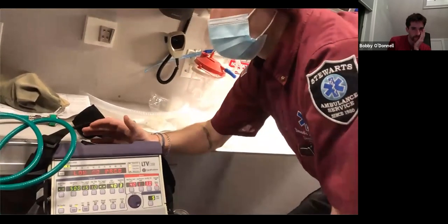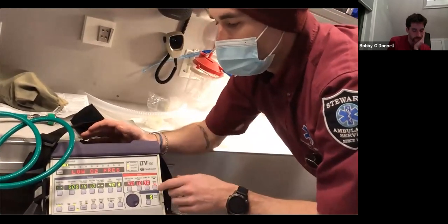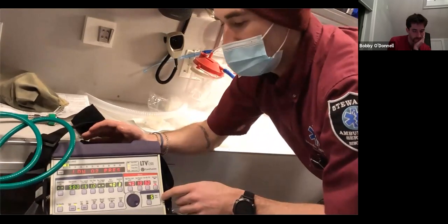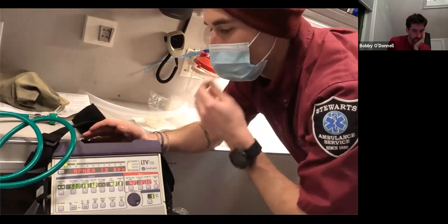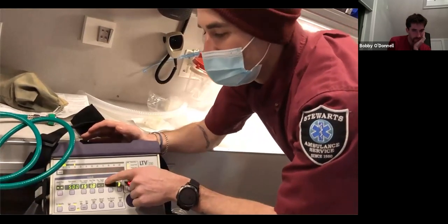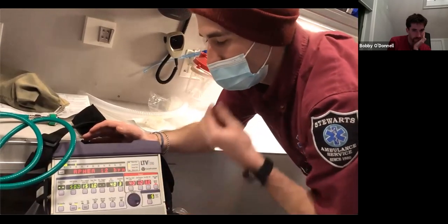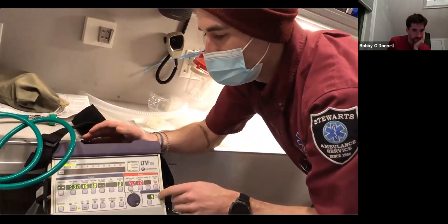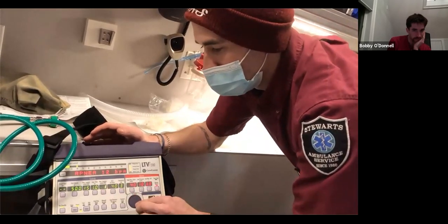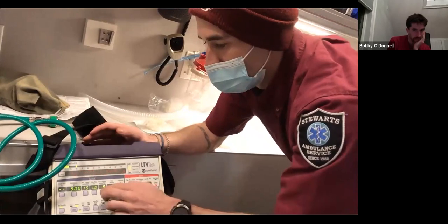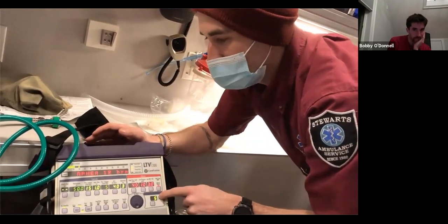So the changes that we make with BiPAP is we want to create an IPAP, so our inspiratory peak airway pressure. And like I said in the presentation, the LTV1200 is additive. So you can see right here, it says centimeters of water plus PEEP. So if we wanted an IPAP of 10, we have our PEEP of 5, so our pressure support is also going to be 5. So that right there is an IPAP of 10 and an EPAP of 5.